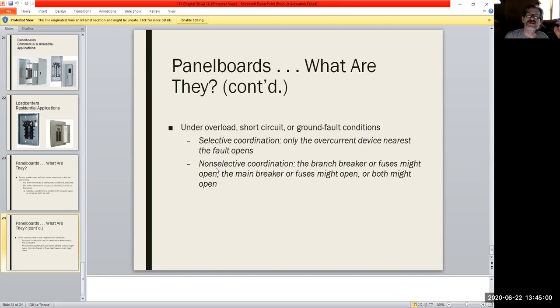But again, it's a matter of planning. As long as you do your math in the beginning correctly, and size everything accordingly for your installation, you shouldn't run into too many problems. It's when you don't, when you just assume and put through a device, and it's underpowered, not quite meeting what you needed it to do, then you might run into trouble. Like if we didn't do our initial calculations, let's say our house needed a 200 amp service and we ended up putting in a 150, we'd have trouble. It just all depends.